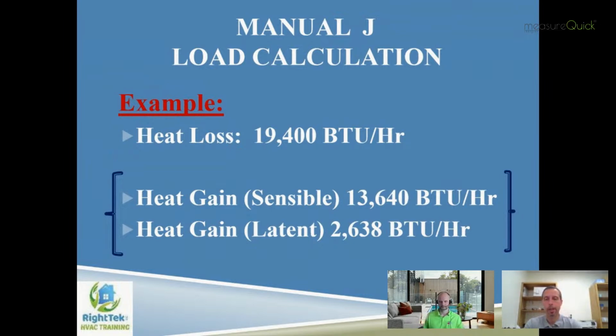So I had the privilege of sitting through a lot of meetings and conversations with some really smart people from the industry, and learned a ton of things that frankly I had no clue about when it comes to inverter heat pumps, variable capacity systems, variable refrigerant flow, and dehumidification. A lot of great knowledge got poured into this over the last roughly 3 to 4 years. All I'm going to try to do is share some highlights today, and of course we'll open it up to conversation. I'll start by walking through the old school, current Manual S way of sizing a basic single stage heat pump system, talk about how we do it now, and then relate that to how the guidelines change in the new Manual S.